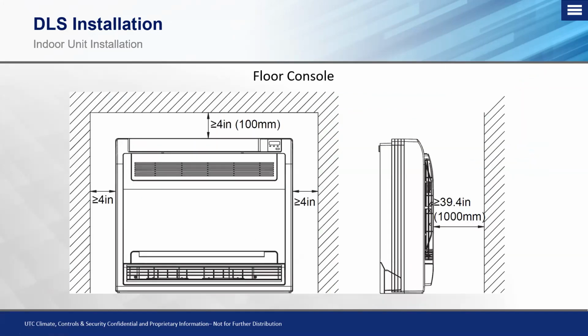For our floor consoles, if we're doing a recessed application where the unit is going to sit back between a wall area, we need to make sure that we have a minimum of 4 inches on the top, on the left, and on the right for service clearance for that unit. One thing we need to consider on the front side is how this unit opens. There are two tabs on the very top, right here and right here, that you push together and the front part slides out.